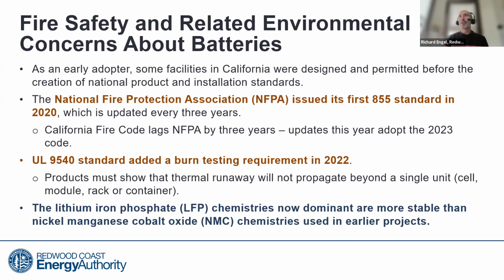In 2020, the National Fire Protection Association, the same folks that do the National Electric Code, issued a standard called 855 that gets updated every 3 years going forward. There's also the Underwriters Laboratories, UL, the ones with the little seal you see on consumer electric products. They have a standard called 9540 that requires burn testing of battery technologies before they can be deployed, so they have to demonstrate that even if a fire starts, it won't propagate across a whole system. The good news is that the lithium iron phosphate chemistries now coming to dominate the market for new projects are proving much more stable than earlier batteries like nickel, manganese, cobalt.